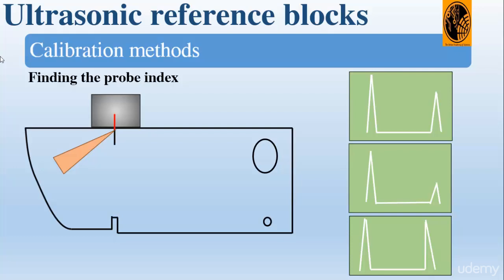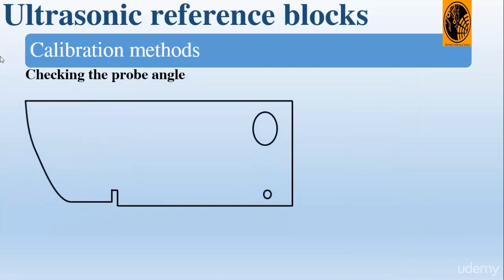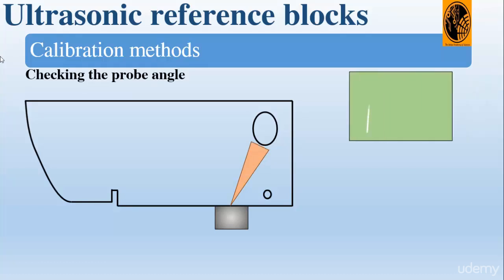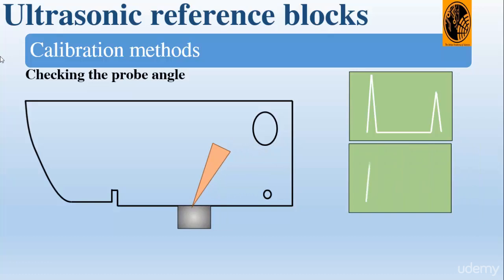Now let's see how we can check the angle of the probe for 45 and 60 degrees. We place the probe on the V1 block approximately adjacent to where the appropriate angle is inscribed and direct it at the plastic insert. As seen in the animation, we obtain the signal from the plastic insert and maximize it by moving the probe backward and forward. We find the position where the probe index coincides with the angle indicated on the side of the V1 block — this will be the angle of the probe.